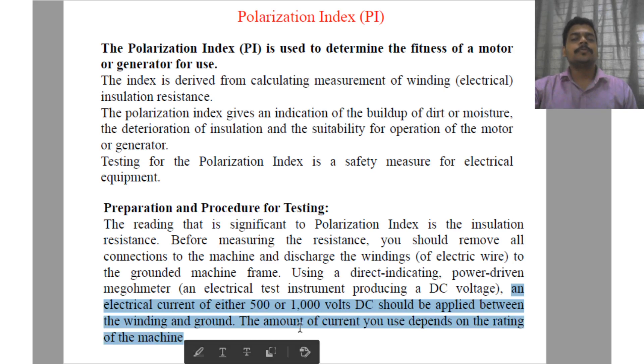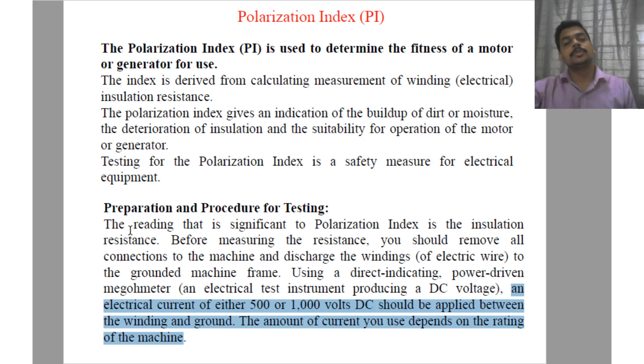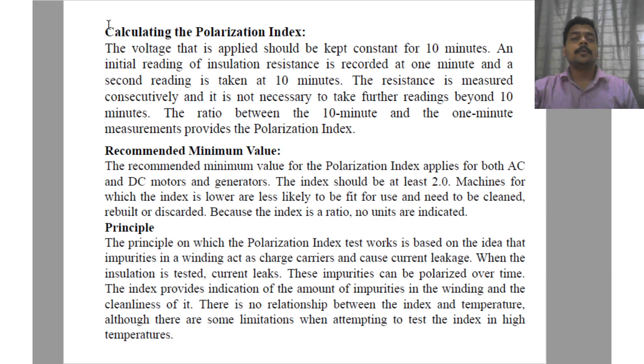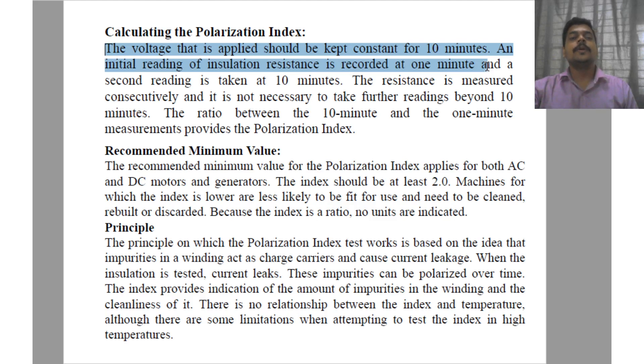The amount of current you use depends on the rating of the machine. The voltage applied should be kept constant for 10 minutes. An initial reading of insulation resistance is recorded at 1 minute, and a second reading is taken at 10 minutes.